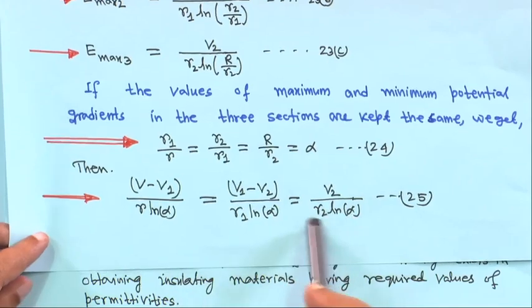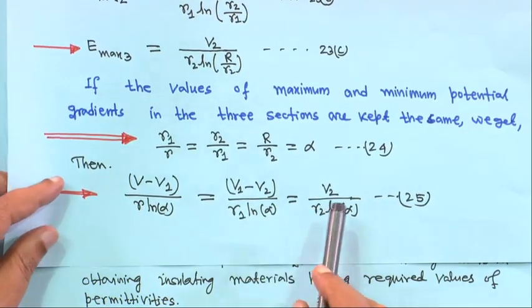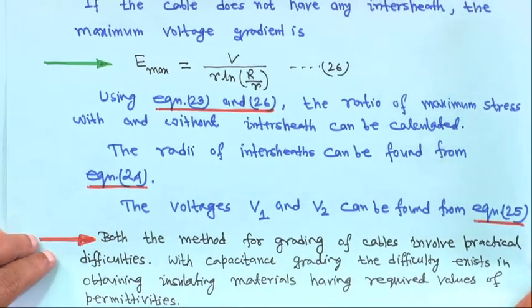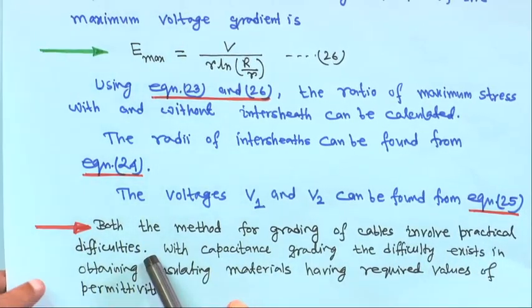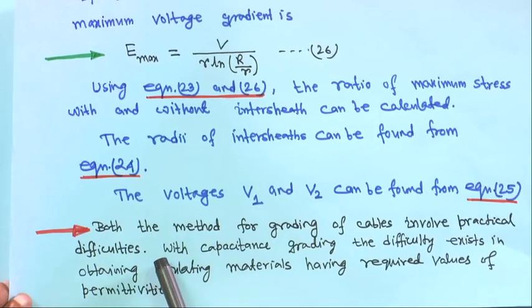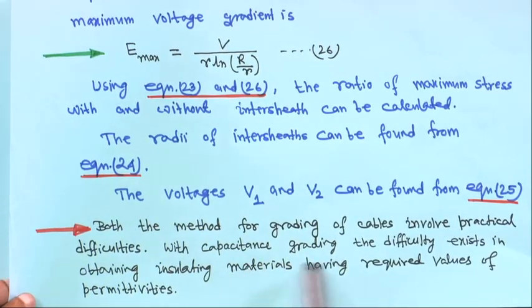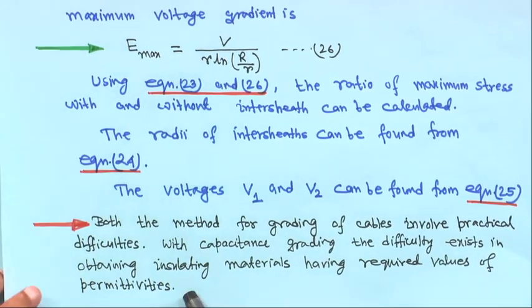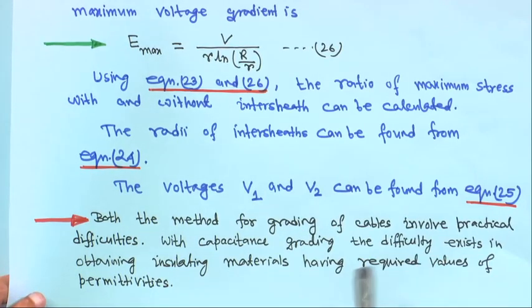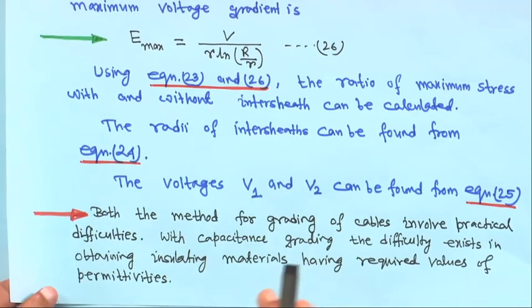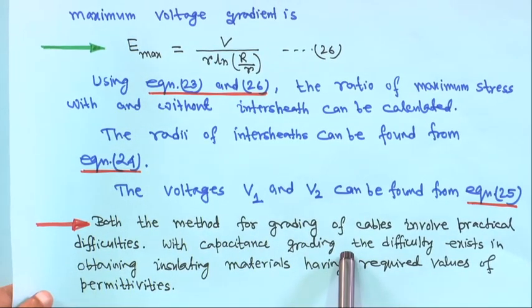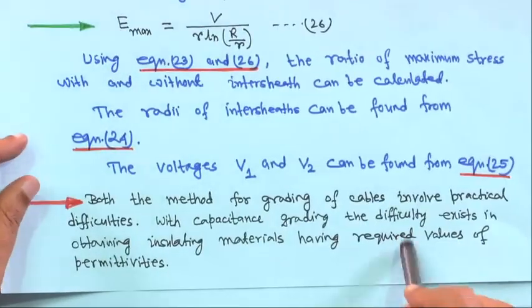Both methods for grading of cables involve practical difficulties. With capacitance grading, the difficulty lies in obtaining insulating materials with the required values of permittivity. For example, rubber has permittivity 4–6 and impregnated paper 3–4 have been suggested, but rubber is very expensive and the cost becomes prohibitive.